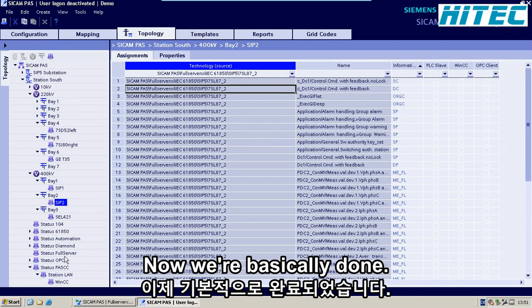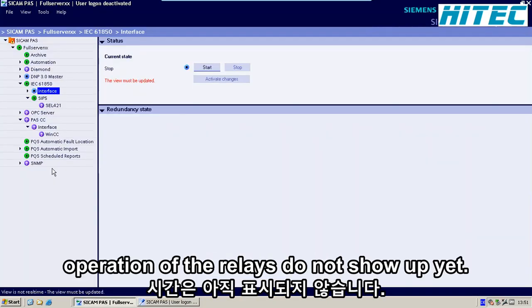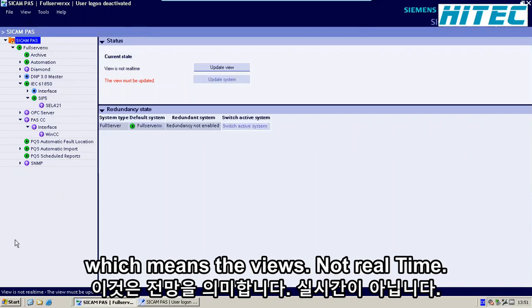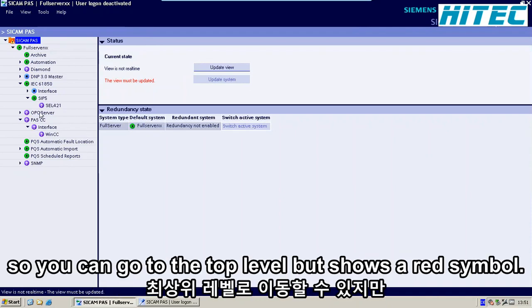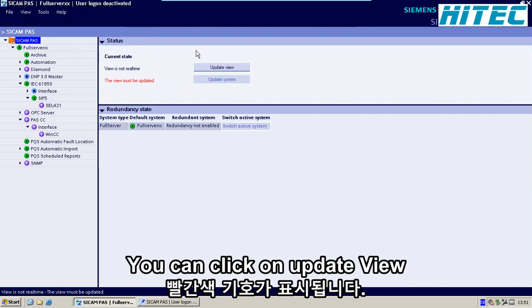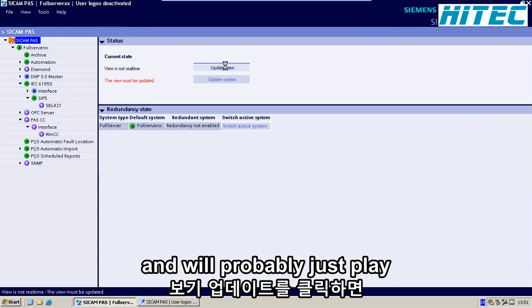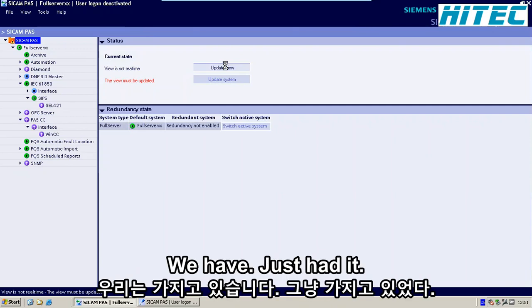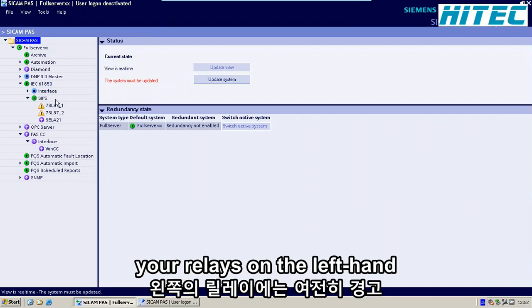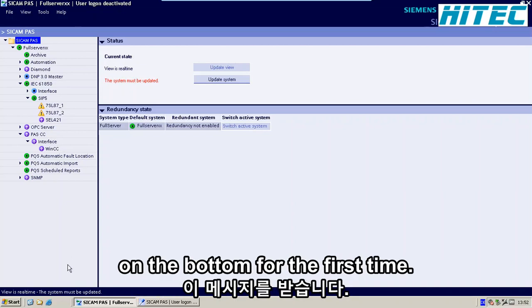Now we are basically done. If you switch to the runtime in SICAM operation, the relays do not show up yet and you see a red symbol, which means the view is not real time. The view must be updated. Go to the top level where the red symbol shows and click Update View. It will display the two relays we just added. The two new relays now appear on the left-hand side, but they still have a warning symbol. The system must be updated. The first time you add a relay to your configuration, you have to update the whole system.